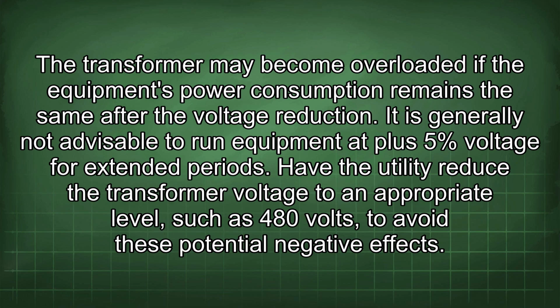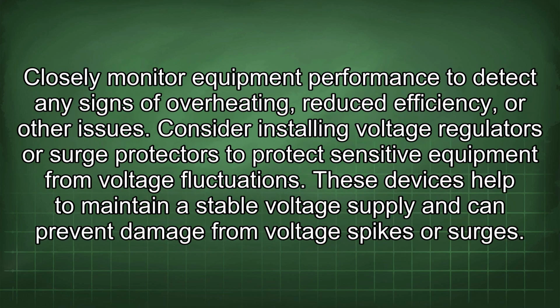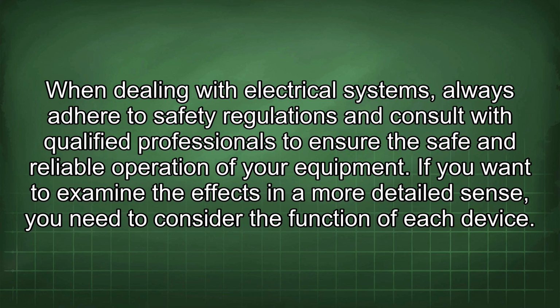It is generally not advisable to run equipment at plus 5% voltage for extended periods. Have the utility reduce the transformer voltage to an appropriate level, such as 480 volts, to avoid these potential negative effects. Closely monitor equipment performance to detect any signs of overheating, reduced efficiency, or other issues. Consider installing voltage regulators or surge protectors to protect sensitive equipment from voltage fluctuations. These devices help to maintain a stable voltage supply and can prevent damage from voltage spikes or surges. When dealing with electrical systems, always adhere to safety regulations and consult with qualified professionals to ensure the safe and reliable operation of your equipment.